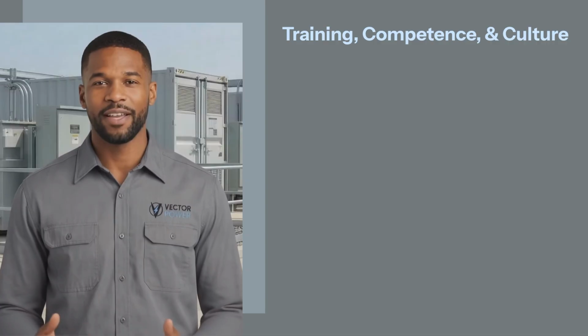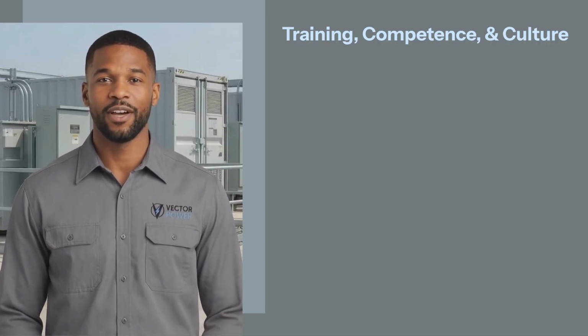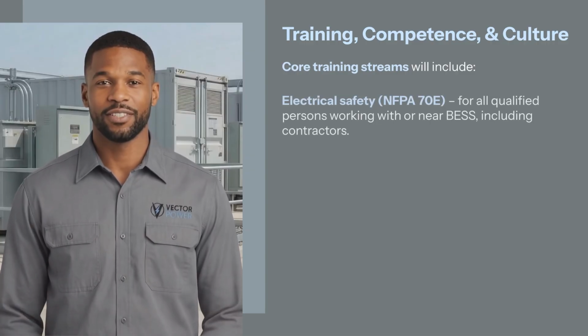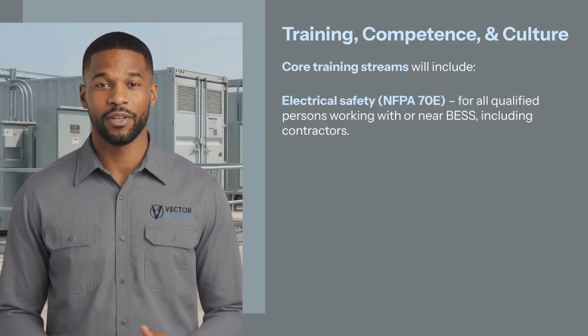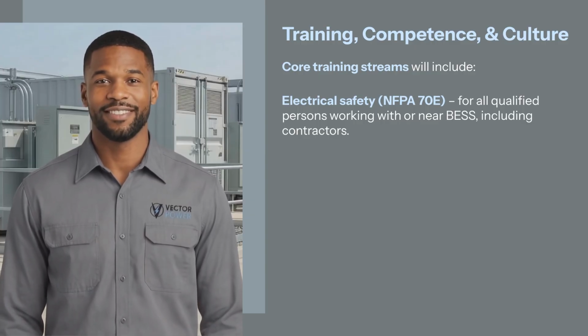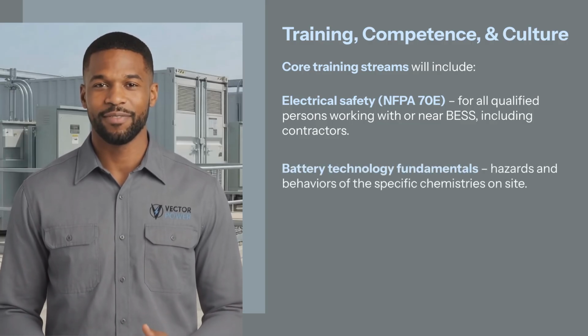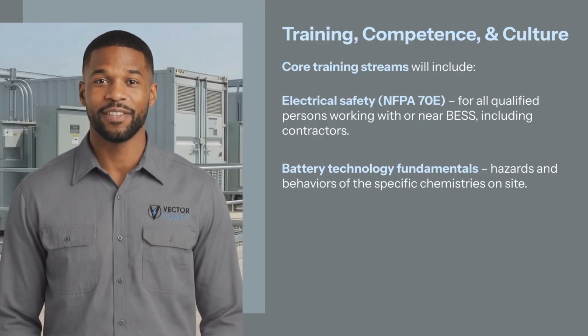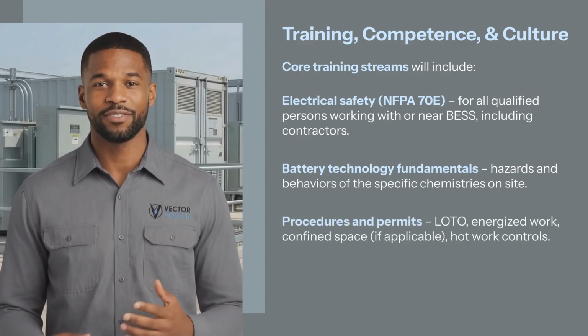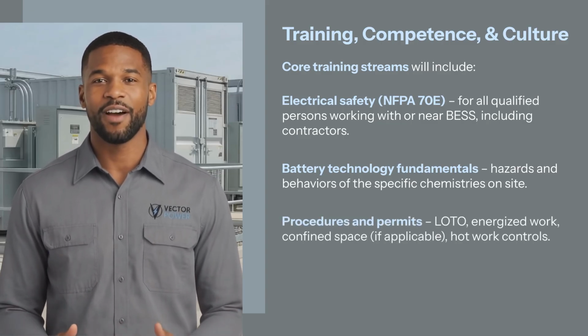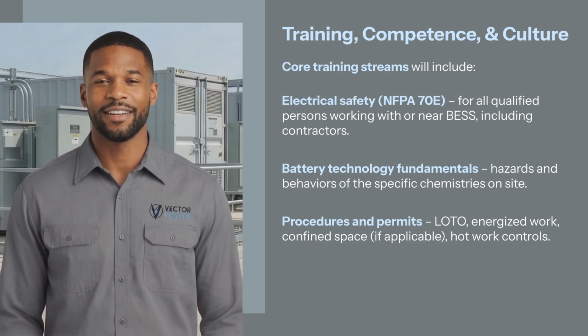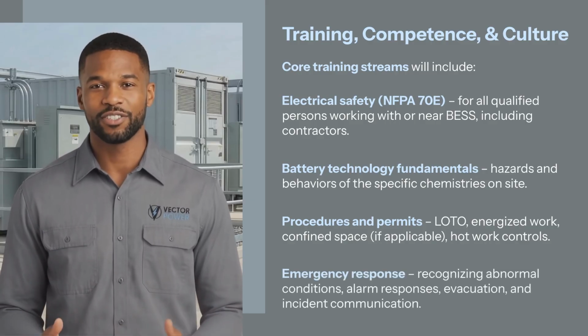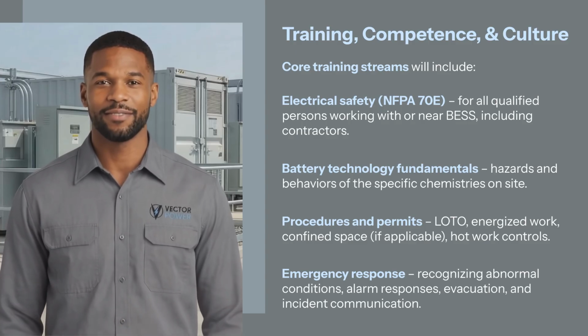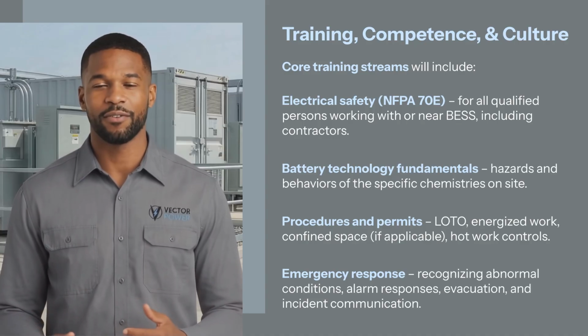Training, competence, and culture. A maintenance and safety program succeeds or fails on people. Therefore, core training streams will include electrical safety, NFPA 70E, for all qualified persons working with or near battery energy storage systems, including contractors. Battery technology fundamentals: this involves an understanding of the hazards and behaviors of the specific chemistries on site. Procedures and permits such as lockout/tagout, energized electrical work, confined space if applicable, and hot work controls. And emergency response: recognizing abnormal conditions, alarm responses, evacuation, and incident communication. Refresher training should be aligned with NFPA 70E revision cycles and significant changes to NFPA 70B and NFPA 855, as well as vendor updates for the installed battery energy storage system.